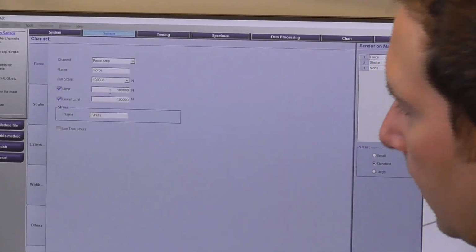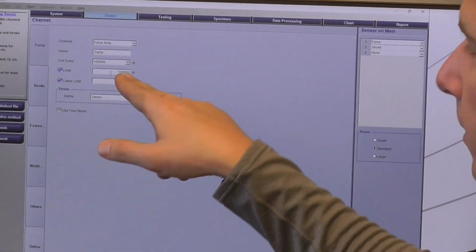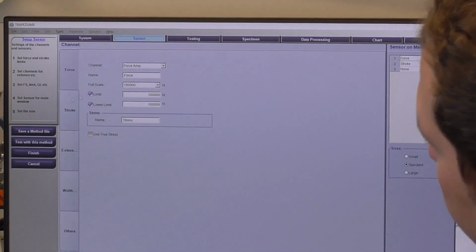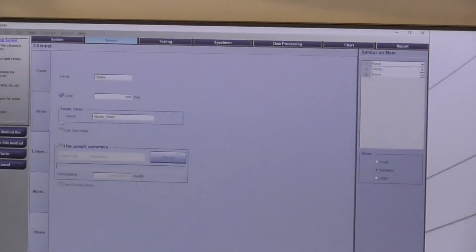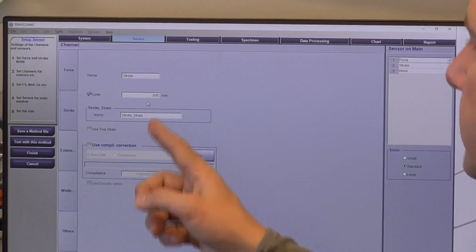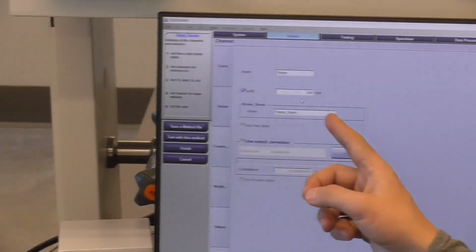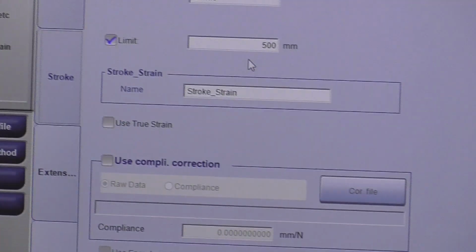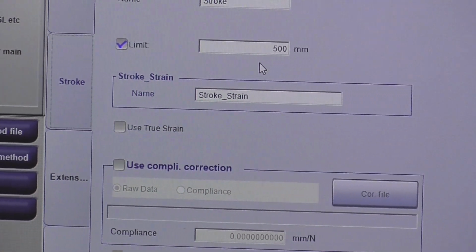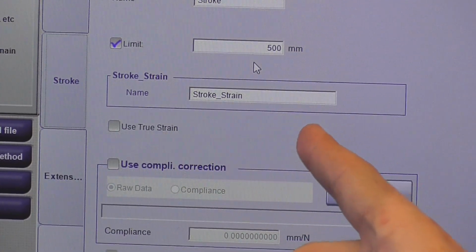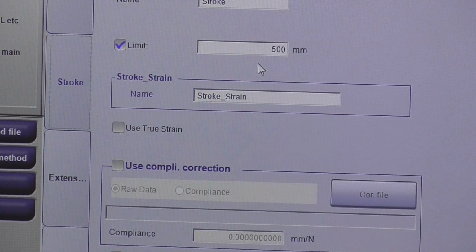So for instance, if you're using your 100 kilonewton 3-point bending jig with your 100 kilonewton load cell, you probably would want to change these values in here just so you don't overload the jig. Stroke is automatically calculated as well, but this is important because this is where you set up your software limit for the stroke.